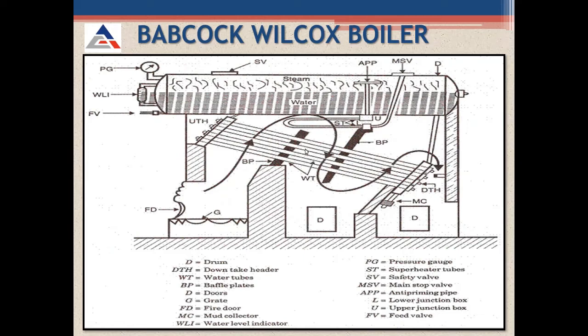The tubes are inclined at some particular angle — not horizontal, not vertical. As water starts heating up it converts into steam and moves towards the uptake header, then back into the drum. This cycle repeats until all the water is converted into steam. There are also superheater tubes to further heat the steam, and an anti-priming pipe to remove moisture content and produce dry saturated steam. Other fittings include a safety valve, pressure gauge, water level indicator, and feed valve.